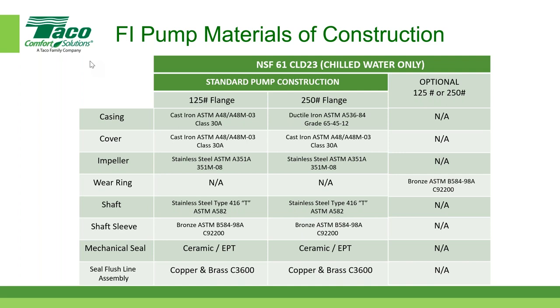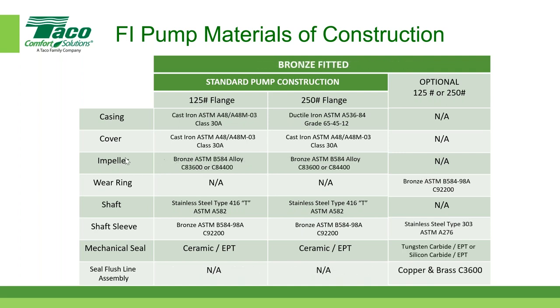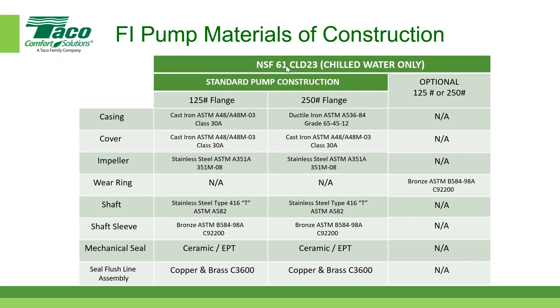But the stainless steel shaft is also standard, whether it's NSF 61 or not, correct? From the previous slide? For the shaft, correct. The shaft is stainless steel. What does change, I believe, is the impeller. When you go to NSF 61, the impeller goes from bronze to stainless steel. So what we call a bronze fitted pump has a bronze impeller. The NSF for domestic cold has a stainless steel impeller. That's correct. Pretty much the only difference besides requiring a flush line. Great. And another great catch.